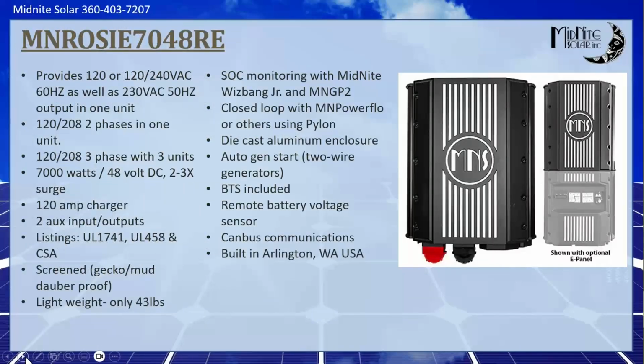So the Rosie is something that we're extremely proud of, super excited. It's a game changer. The thing is a powerhouse. It's very versatile. So a single Rosie can do 120 volts, 60 hertz, 120/240, 60 hertz, 230, 50 hertz, or 120/208 two legs of three phase, 60 hertz. But if you need three-phase, full three-phase 208, we can do 3 Rosies. So it's a very, very versatile product.